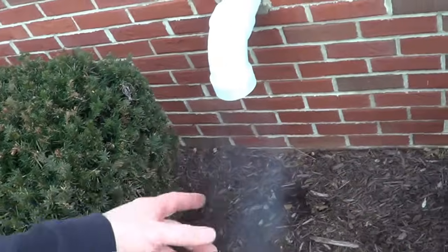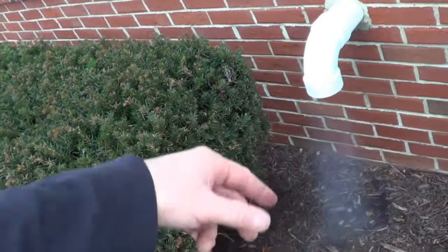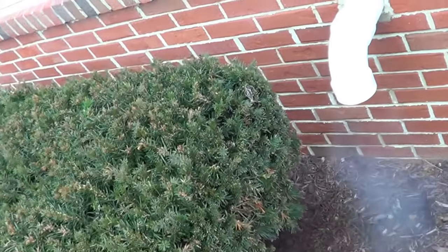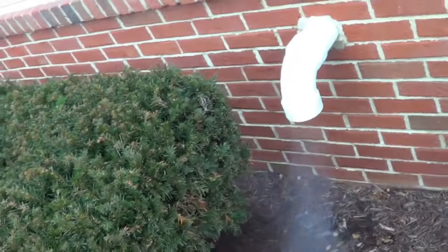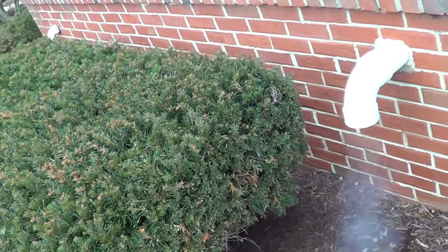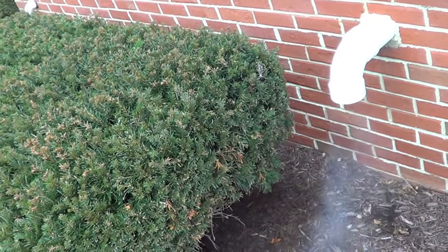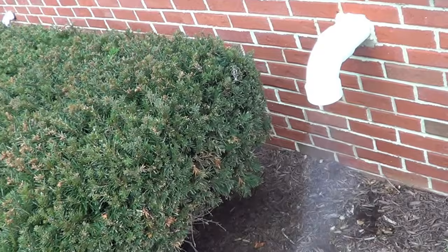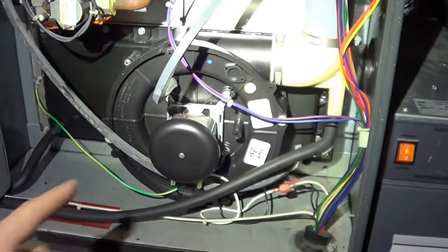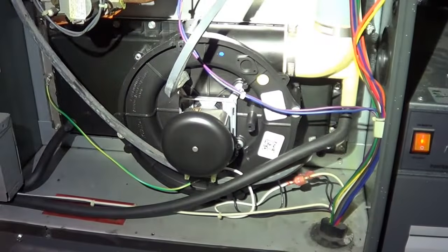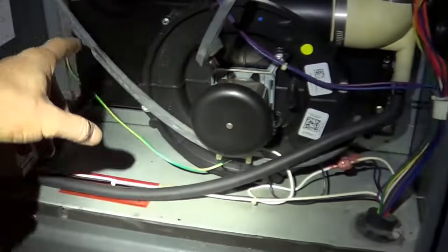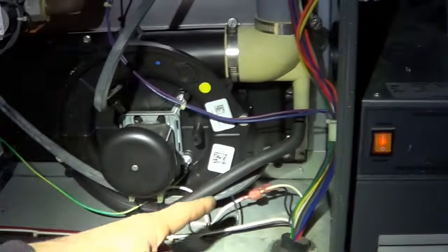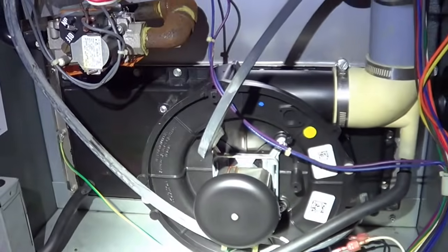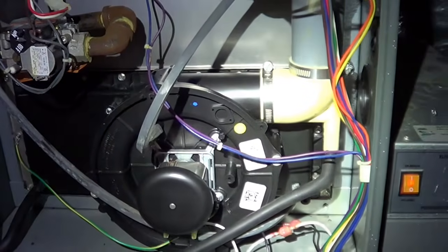Now when it gets really clogged, just one breath is pretty deadly on that exhaust, so you do want to be careful. If it smells like it's gonna kill you in 1 second, it's very clogged, and it's basically the furnace is destroying itself right away. It's pretty easy to pull it apart and actually clean the secondary heat exchanger. Pull off the fan, take off all the screws on the header plate, pull the header plate, and then just go after it with some soap and water. So I'll show that next.